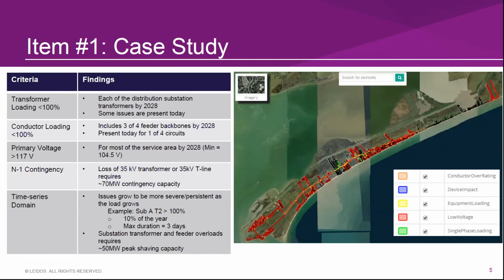In this case, we had transformer loading over 100%, conductor loading over 100%, voltage less than 117, and ultimately a big cost driver was that they wanted N-1 contingency for this area.